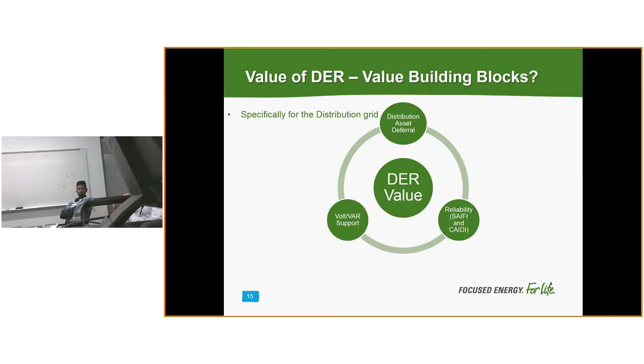One other approach is similar to an on-off scenario, like when we discussed conservation voltage reduction and VVO—running with and without voltage reduction to capture the difference in performance. You can do the same here: run your network model with no DER for the next 5 years and note the violations. Then add DER to your assets, rerun, and iterate to see where violations are eliminated and where that value comes from, capturing it in watts and vars.